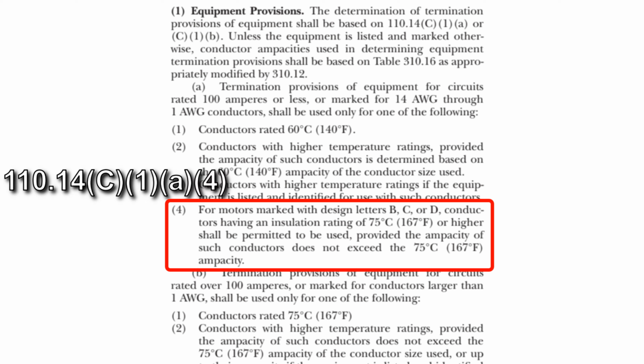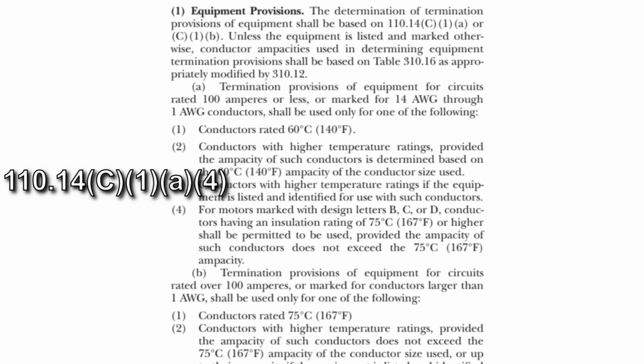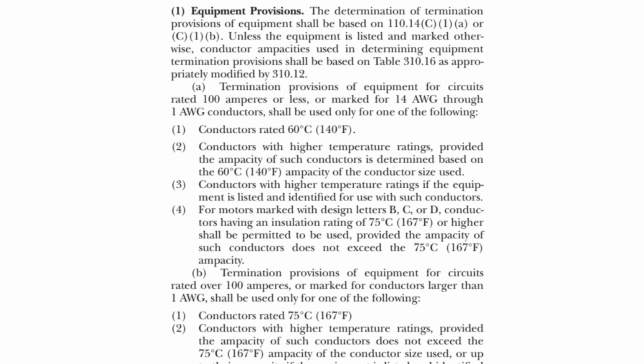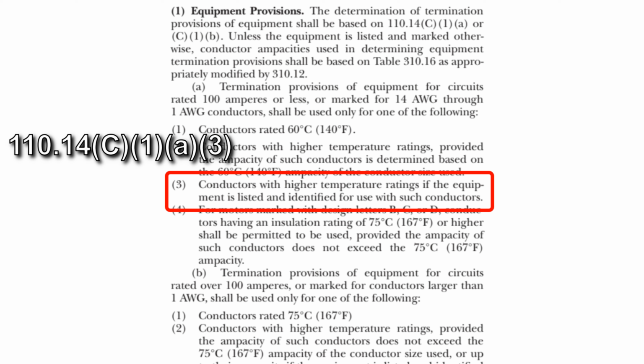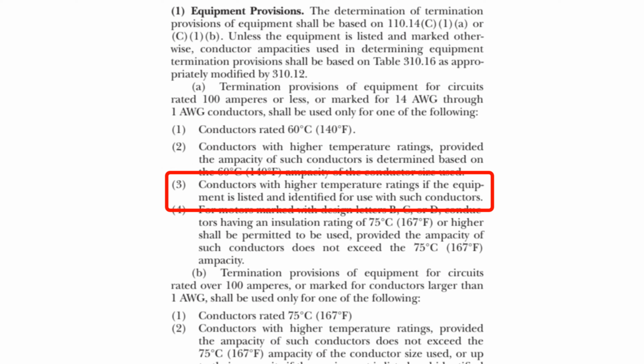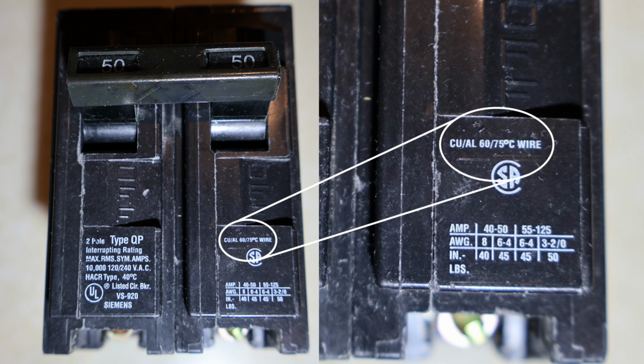4. For motors marked with design B, C, or D, conductors having an insulation rating of 75 degrees C or higher shall be permitted to be used, provided the ampacity of such conductors does not exceed the 75 degree ampacity. So if we're wiring a B, C, or D motor, 100 amp or less circuit, we can use 75 degree or higher rated conductors, as long as we use the 75 degree column ampacity. 1, 2, and 4 don't apply to the circuit we're working, but 3 does. For our example circuit, we can use conductor ampacities with a higher than 60 degree rating, because the equipment we're wiring is identified for use in the 75 degree column.